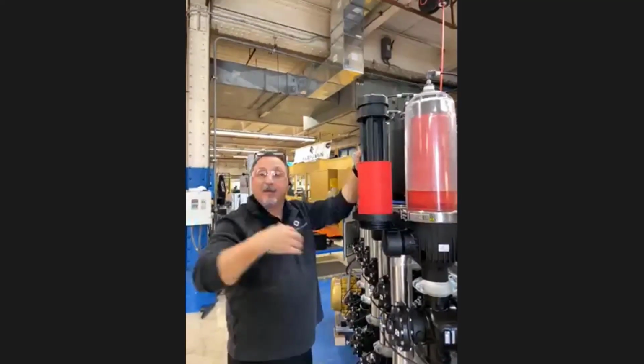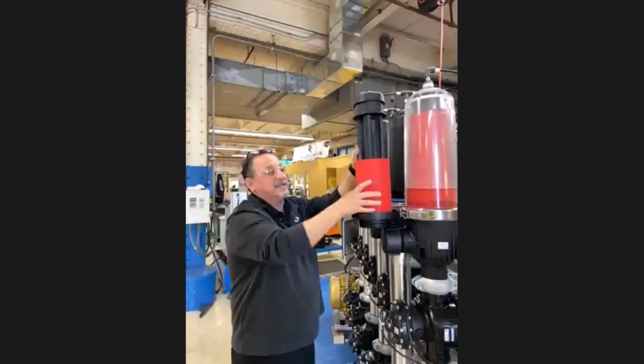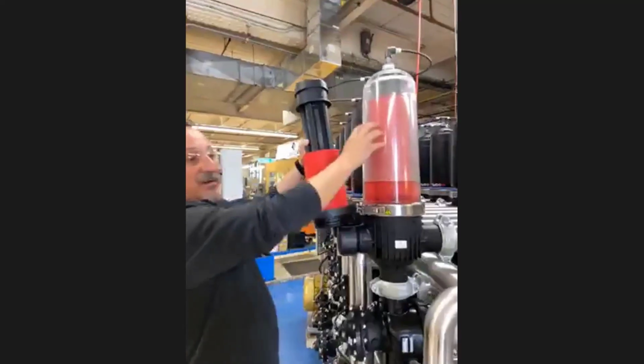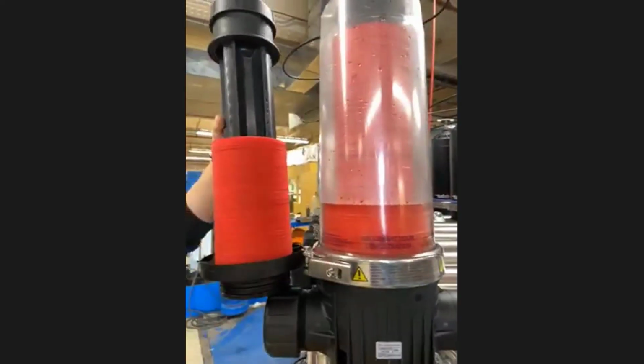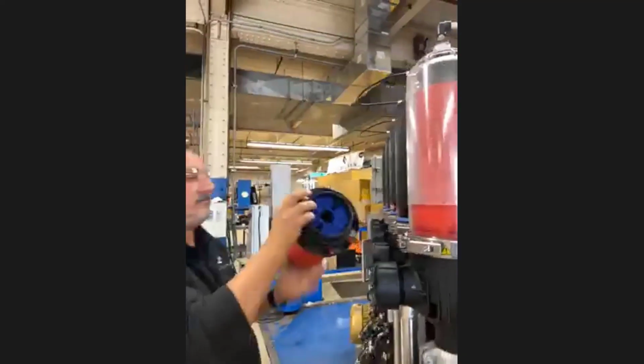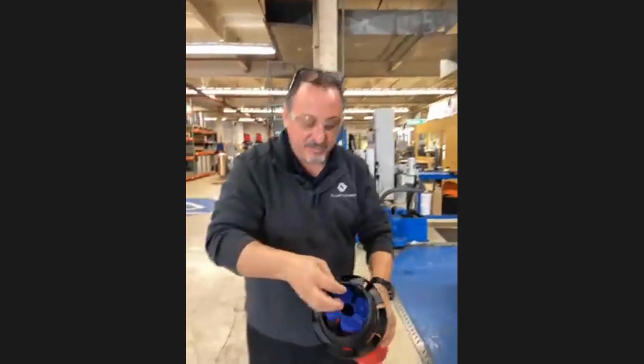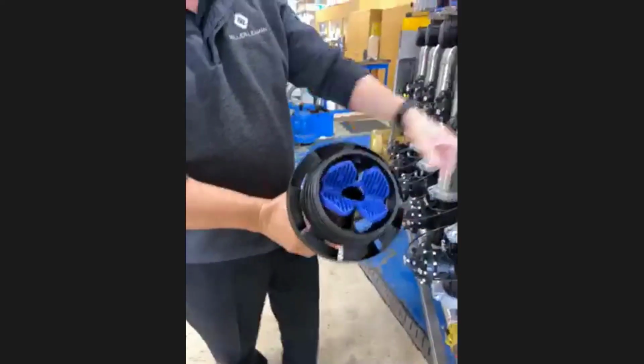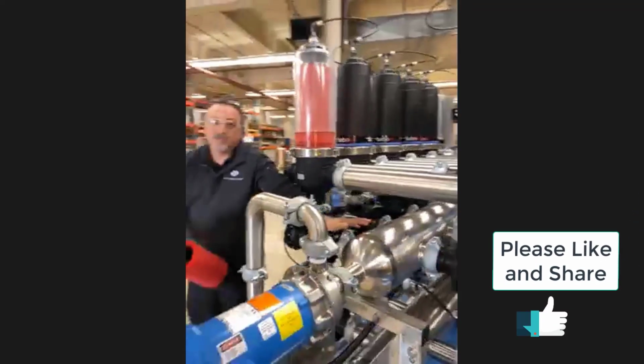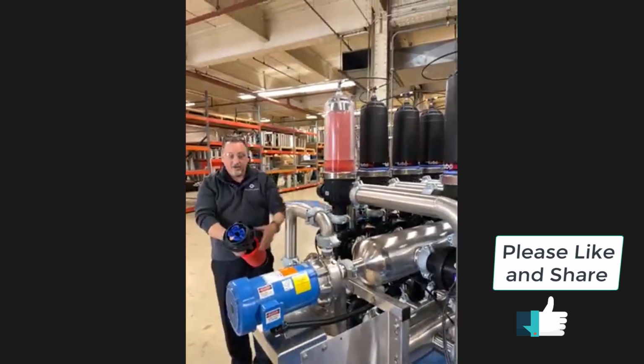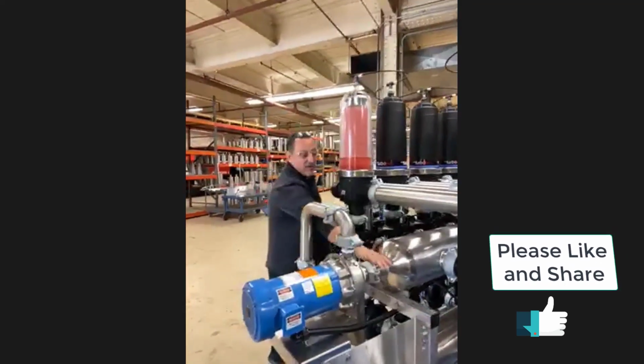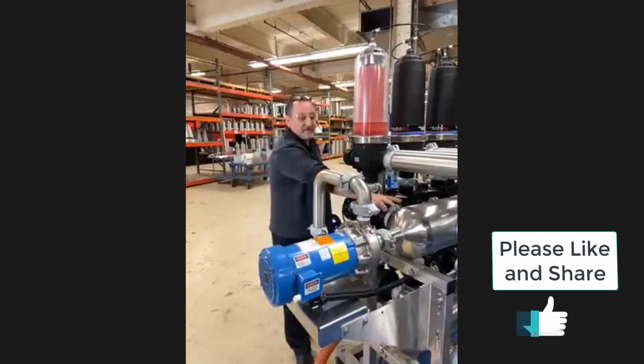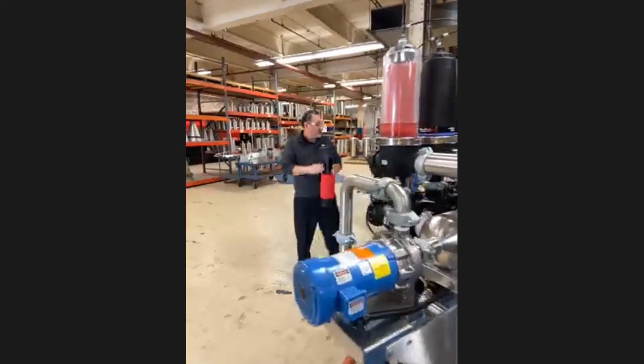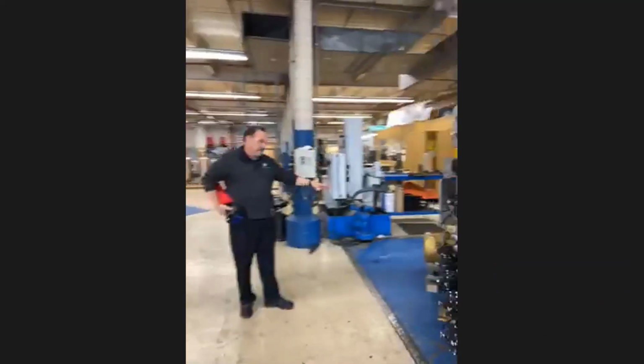Then the organic or the floatable materials cling onto the disc, and you'll be able to see this disc get a little bit darker in some areas where they cling onto the disc, because then the water goes through the disc, out this check valve, which is open during filtration, just like that, open, and down into the clean water manifold, which is right here. The clean water manifold then sends it back to the cooling tower. We do have a small booster pump that's hooked up to the clean water manifold because we're using clean water to backflush ourselves. So in turn, we typically use a lower head pump than a sand filter.